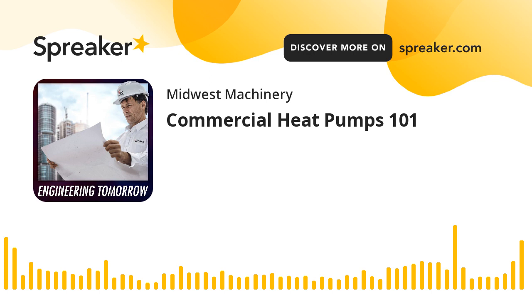So once you get there, now you're going to go look at your plant. Okay, so I have 100 tons of cooling. I have to size my cooling towers for 85 tons. So most places put some sort of redundancy in. So I'm not going to do 100% redundancy. I mean, you certainly can if it's important, maybe it's a luxury condo, and if one cooling tower goes down, you want to be absolutely certain that on a design day it can handle the whole load. So if that's the case, then you would size probably 2 cells of cooling tower, each sized for 85 tons. That way, if one goes down, one can handle the whole load on design day.